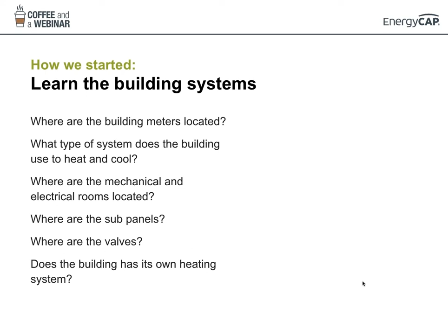When you first start, you have to figure out where the meters are located. What type of systems does the building use to heat and cool—a rooftop unit, a dual duct system, single duct, or multi-zone unit? Where are the mechanical rooms located? Some buildings have a mechanical room on each floor, others one giant one in the basement. You need to be able to describe where the problem is if you see one.